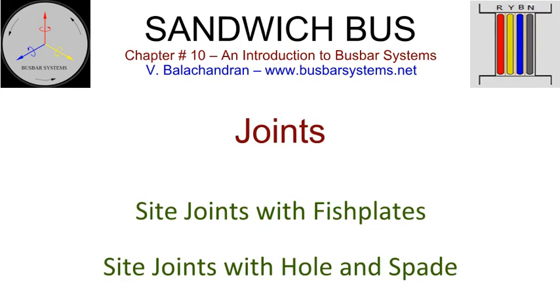Joints. The conductor joint in the run of the busways is a unique design feature. An insulated bolt runs through all the conductors of all phases of conductors located in a site joint assembly. Most of the joints have only one bolt. In a connection where there is more than one run, up to 3 runs, each run will have a bolt at the joint. Some manufacturers provide up to 3 bolts per joint when the width of the conductor is significantly large. There are 2 methods of joining the conductors of 2 adjacent sections.